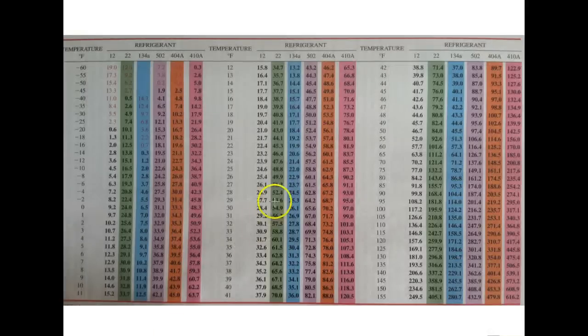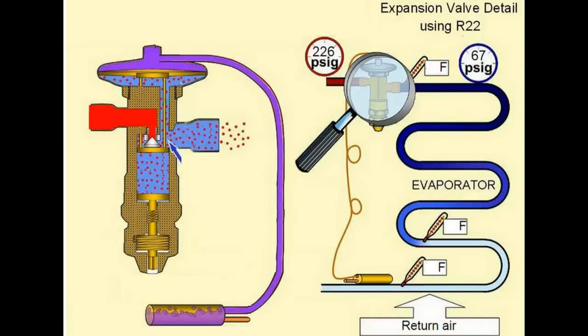So 40 degrees, let's find it on our chart here, is 67, 68.5 PSIG. So at 67 PSIG, both in the sensing bulb and the evaporator line, we have 67 PSIG as the closing force, 67 PSIG as the opening force. And we have no superheat whatsoever at this point.